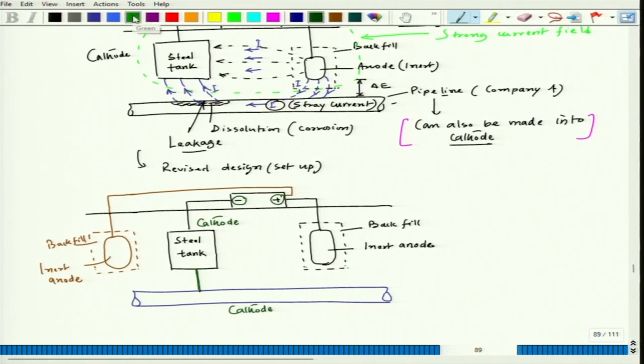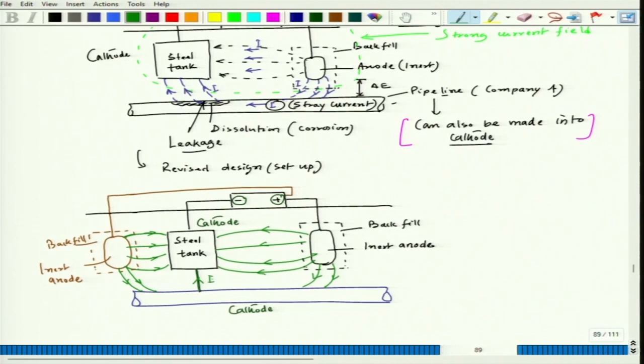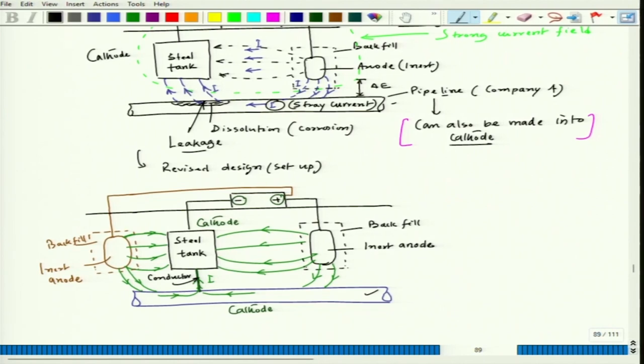The current flow direction would flow from the anodes through the electrolyte into both structures. The current follows the conductor path, and now this pipeline also becomes cathode. So the steel tank and the pipeline can both be protected by this kind of anodic arrangement.